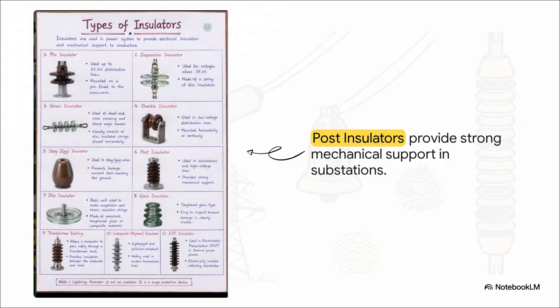But what happens when you need high voltage insulation combined with rigid, unmoving support right from the ground up? Enter the post insulator. Unlike those hanging suspension strings we just talked about, post insulators look like thick, sturdy columns. They are specifically used in substations and on high voltage lines where you need absolutely rock-solid stability, providing the extreme mechanical support needed to keep heavy, dangerous equipment firmly in place while making sure all that high voltage stays completely isolated.